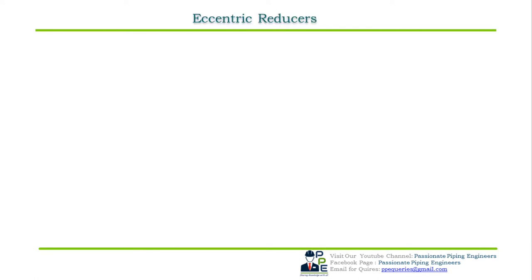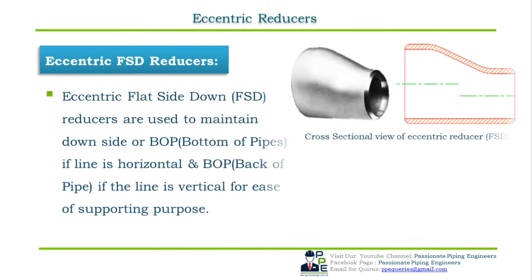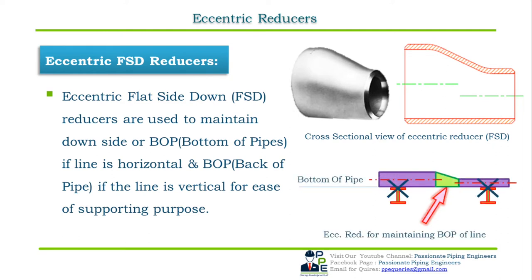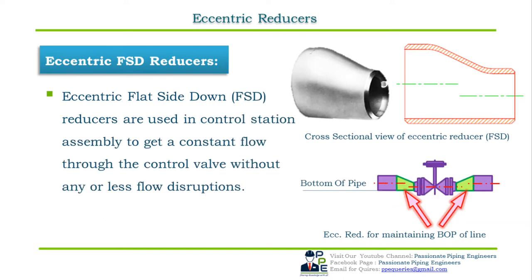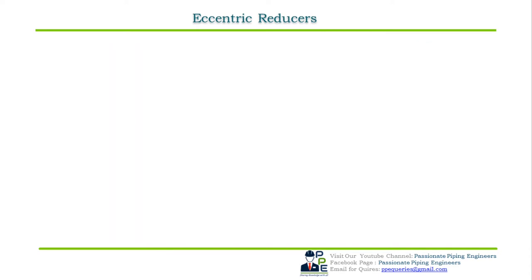Eccentric flat side down (FSD) reducers are used to maintain the downside or BOP (bottom of pipe) if the line is horizontal, and back of pipe (BOP) if the line is vertical, for ease of supporting. As seen in the figure, the bottom of the pipe is maintained for supporting purposes. Flat side down reducers are also used in control stations to get a constant flow through a control valve with minimal flow disturbance.